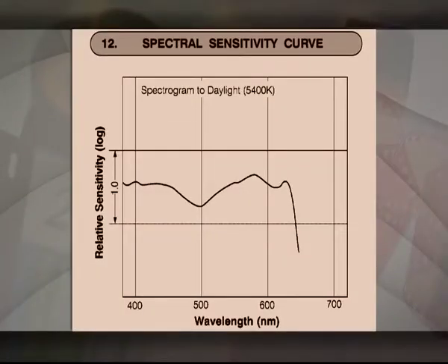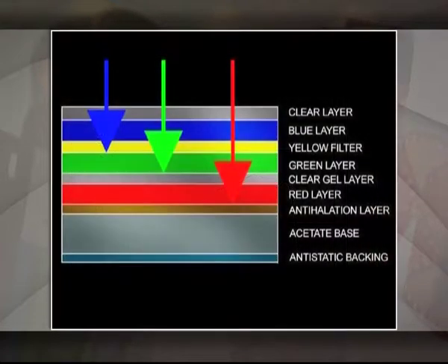Light color, wavelength. Film is not equally sensitive to all wavelengths, colors of light. The spectral sensitivity is a characteristic of film that must be taken into account in selecting film for use with specific intensifying screens and cameras. In general, the film should be most sensitive to the color of the light that is emitted by the intensifying screens, intensifier tubes, cathode ray tubes, CRTs, or lasers.